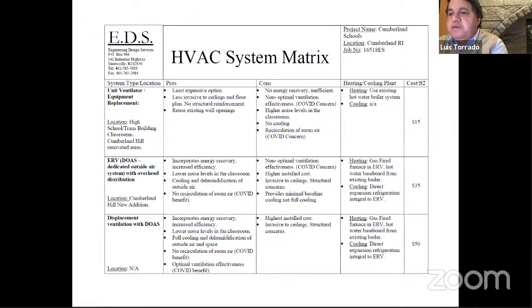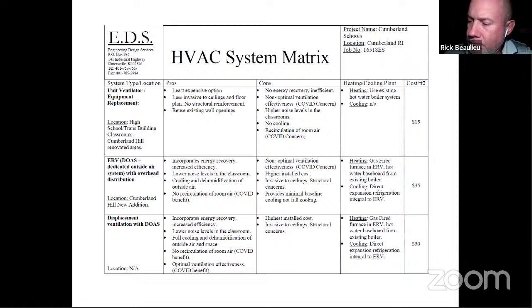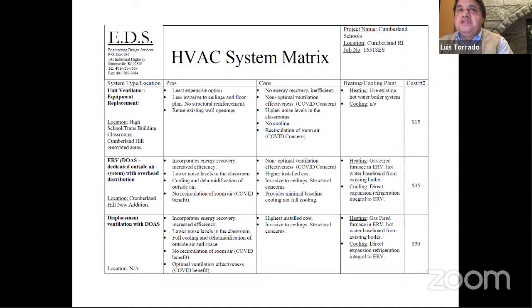Yeah, no, but please let me finish. Sure. We've gone through this in projects in Cumberland and really set the standards for the state, where we had an acoustical engineer go out and test different units, applying them to the space. The result was that in order to comply with the CHPS sound requirements, you needed to get a bigger, more powerful unit ventilator that only ran on low, so that it complied with the required air exchanges while running on low. And so that's the change that we're doing. It is the same system, but a higher grade of unit ventilator.